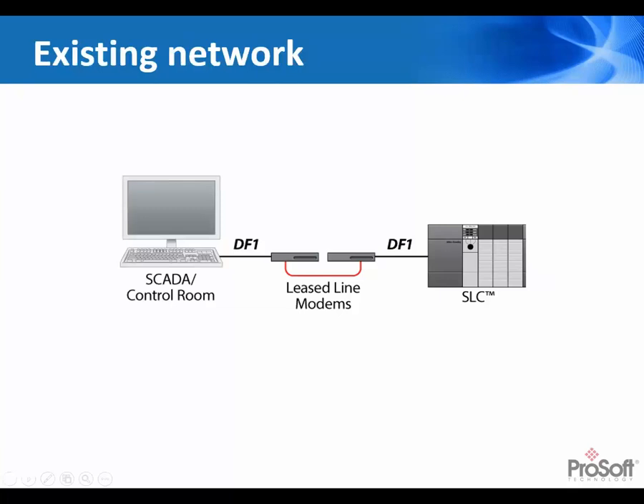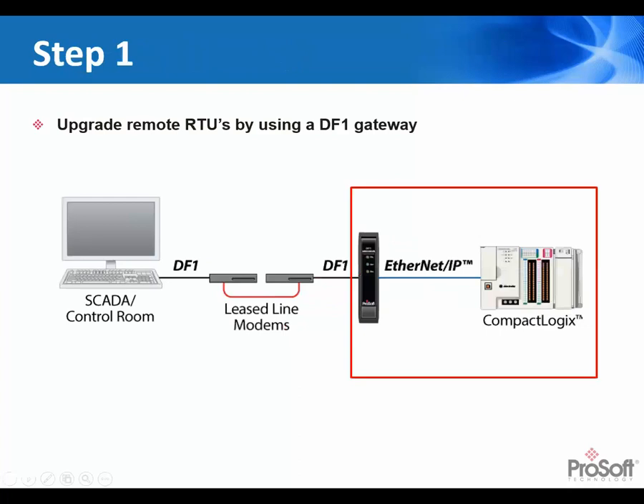So the migration or modernization pathway for this could be to update the RTUs to use the new modern Compact Logix PLCs, which don't have DF1 ports anymore. They can retain the existing infrastructure by using our modernization gateway for DF1 - still talking to the SCADA system over DF1, still using the leased telephone lines over DF1, but then going into Ethernet IP. So you're beginning to modernize the RTU systems while also introducing the Ethernet IP network.